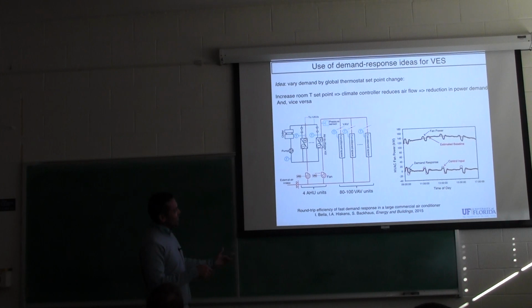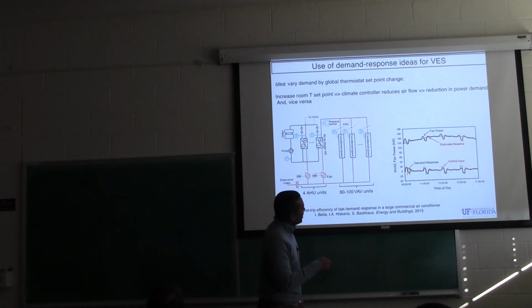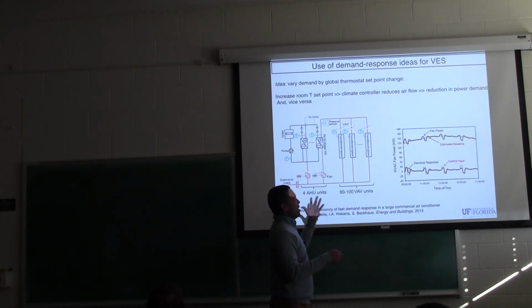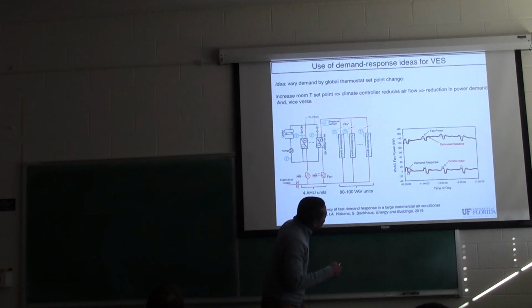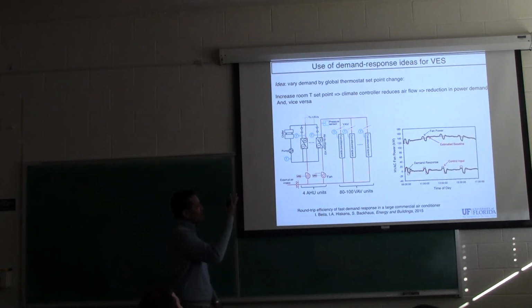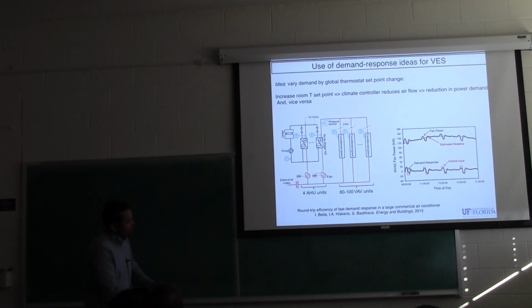So what happened was that they did that, and because now they don't know what the baseline is - this is 9 to 11, two hours - you can see they are trying to do 20 minutes up and down. They're changing the set points, keeping them for 20 minutes, then changing again, and the power goes up and down.